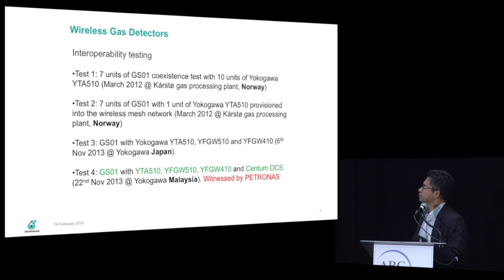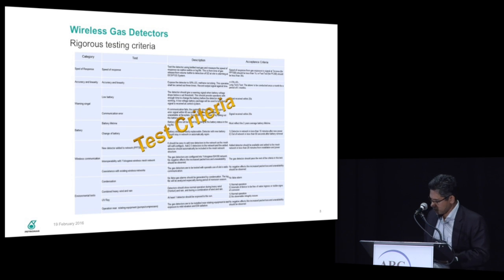Wireless gas detectors. As I mentioned, we did a market research on the existing possibility of wireless gas detectors in the market. Remember, this is 2012. We had 7 units of gas detectors tested in the Yokogawa office in the plant in Norway. There was a second test in the Norway area also with the Yokogawa system, and the third one in Japan. And test number 4 was done in Malaysia, at Yokogawa Malaysia, witnessed by Petronas, by my team.